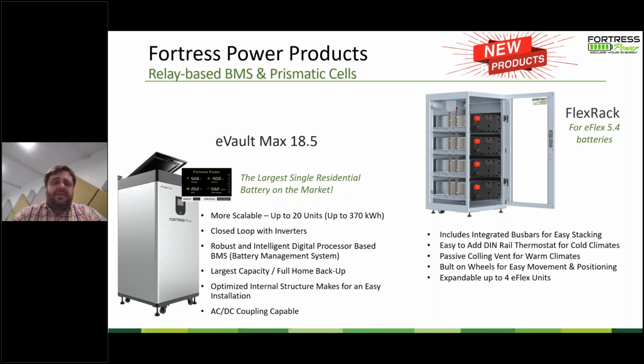The eVault Max now stacks up to 20 units, meaning you can parallel up to 20 of these eVault batteries together. Looking at which batteries we work with closed loop that also scale up, the eVault starts as a residential battery and scales all the way up to about an 80 kilowatt output commercial three-phase 208 battery project.